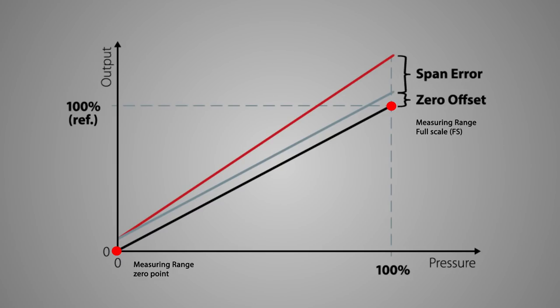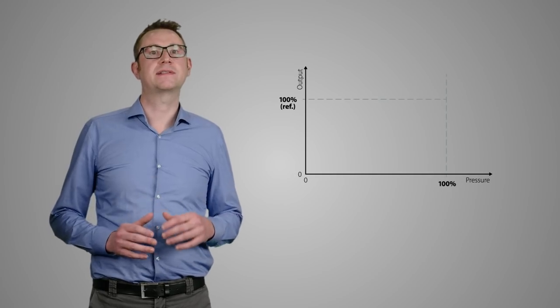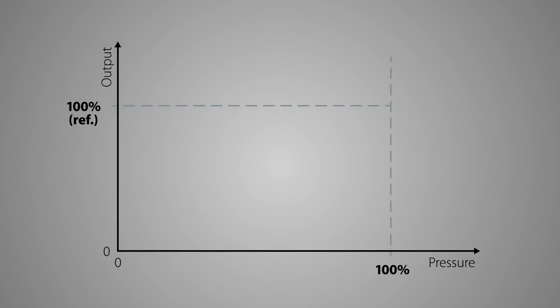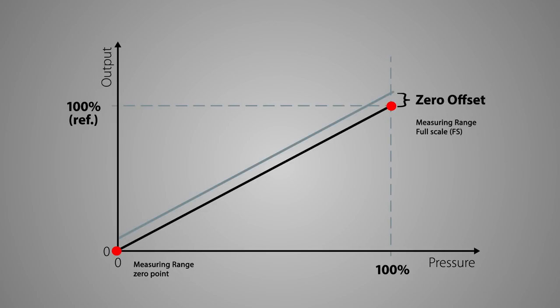Looking at the errors at reference temperature, we are talking about the zero offset and span error. Each measuring device is calibrated to a certain range. This measuring range includes a starting point, the so-called zero point, and an end point, which is called the full scale value. The zero offset describes the error of the output signal at the zero point value. For a relative pressure measurement, the zero point corresponds to the point without any pressure applied.